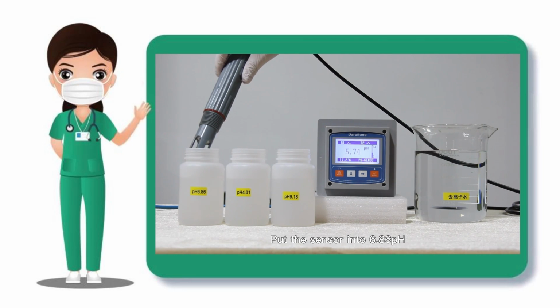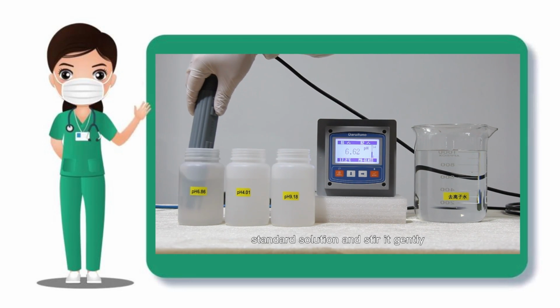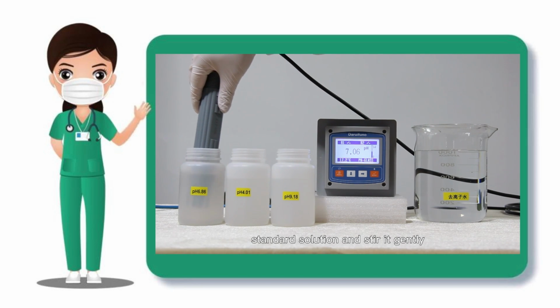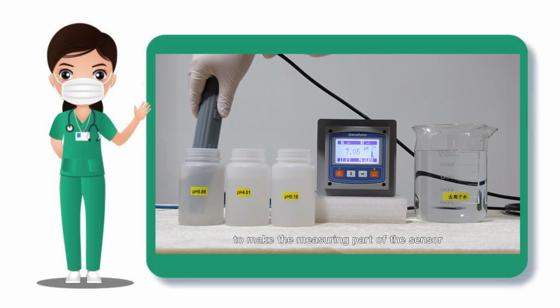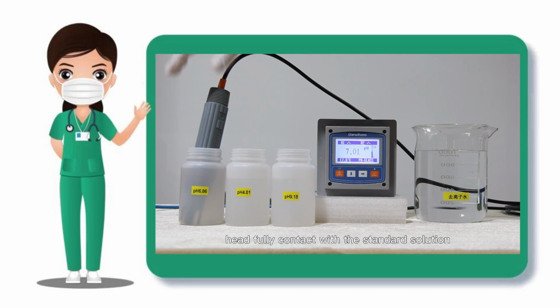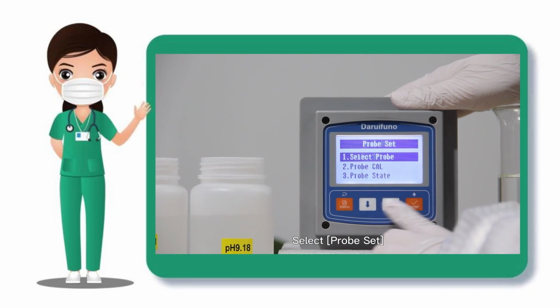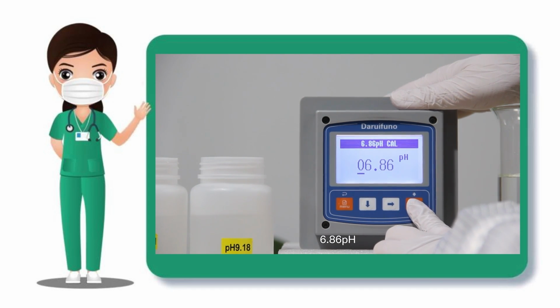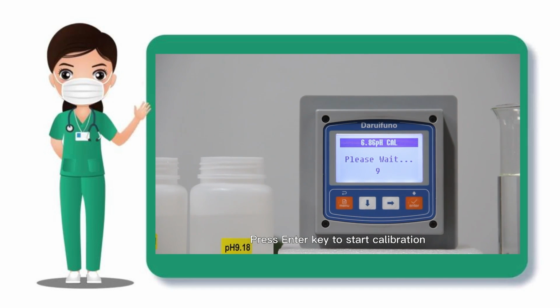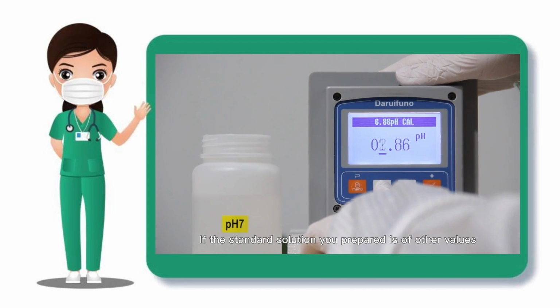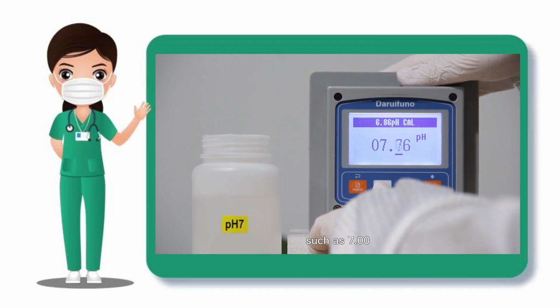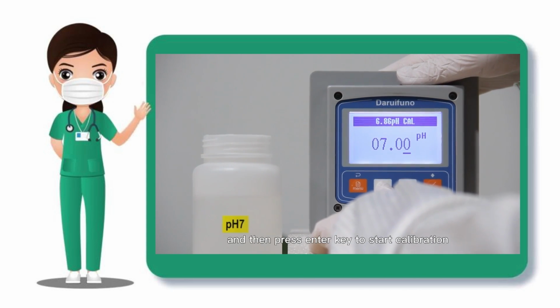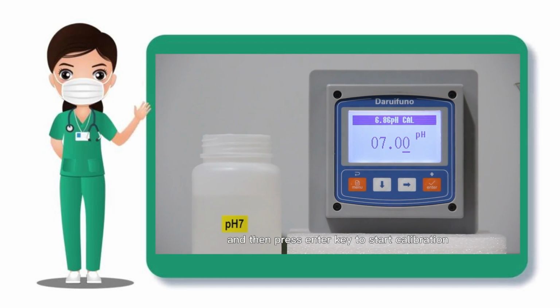Put the sensor into the 6.86 pH standard solution and stir it gently, to make the measuring part of the sensor head fully contact with the standard solution. Select probe set, probe cal, 6.86 pH. Press the enter key to start calibration. If the standard solution you prepared is of another value, such as 7, please change 6.86 to 7, and then press the enter key to start calibration.